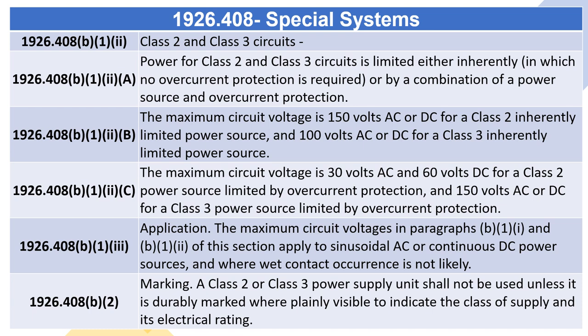1926.408(B)(1)(iii) — Application. The maximum circuit voltages in paragraphs B.1.i and B.1.2 of this section apply to sinusoidal AC or continuous DC power sources, and where wet contact occurrence is not likely. 1926.408(B)(2) — Marking. A Class II or Class III power supply unit shall not be used unless it is durably marked where plainly visible to indicate the class of supply and its electrical rating.